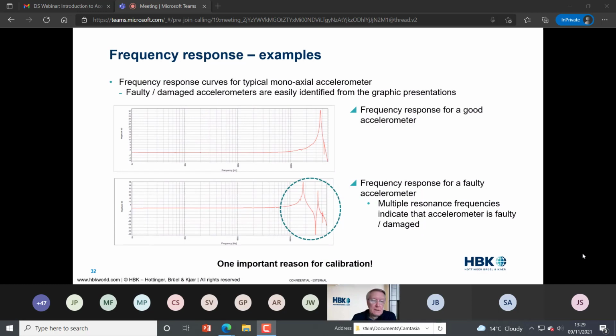One very good reason for doing a full calibration, as I mentioned earlier with regard to dropping accelerometers, is that this calibration, shown on the bottom trace, has clearly shown that some damage has occurred to the accelerometer, in that the resonance frequency has been spoiled completely and another resonance added due to damage.